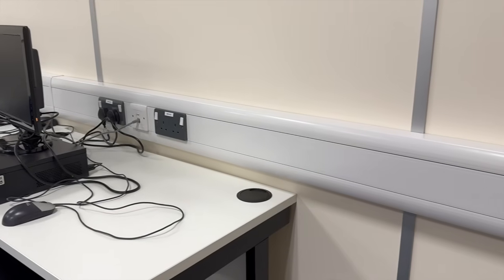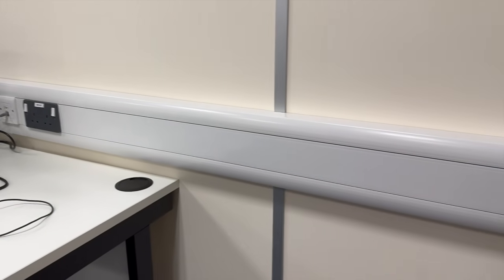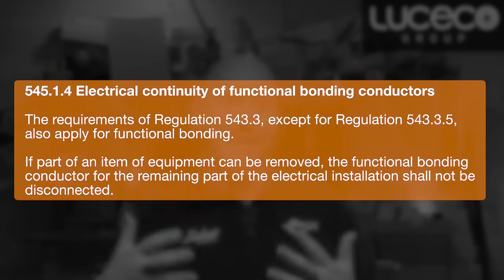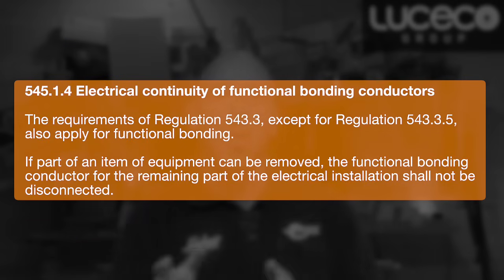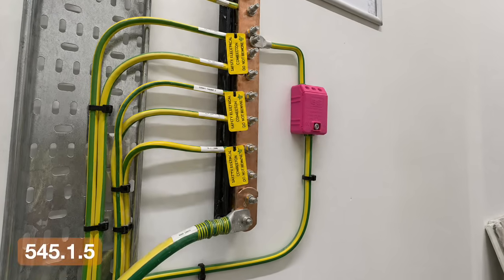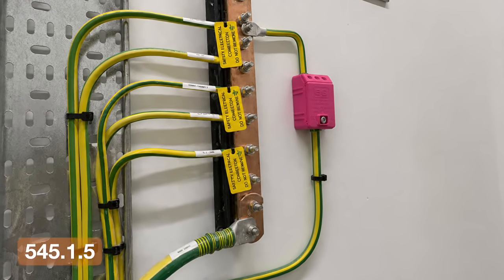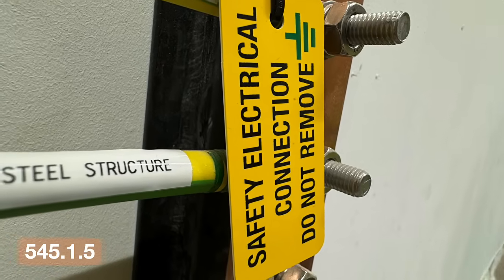So this is driven by how the system behaves, not just a table of values. Continuity is also important. The system must remain intact even if equipment is removed for maintenance. And if a conductor performs both protective and functional roles, it must meet all the requirements of a protective conductor. So the key takeaway here is that functional earthing is now clearly defined. It has a specific role and it needs to be considered separately from protective earthing when you are designing and installing systems.